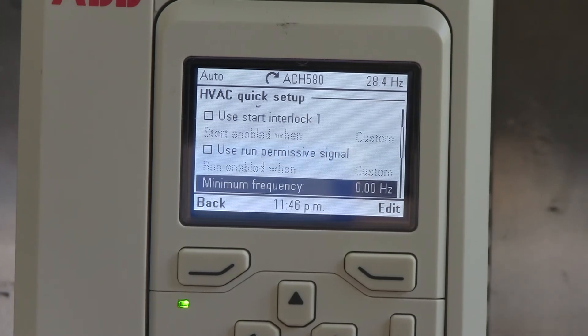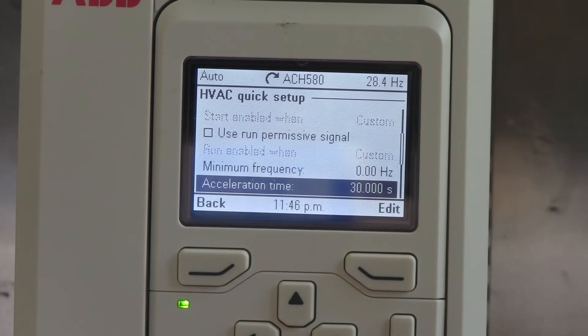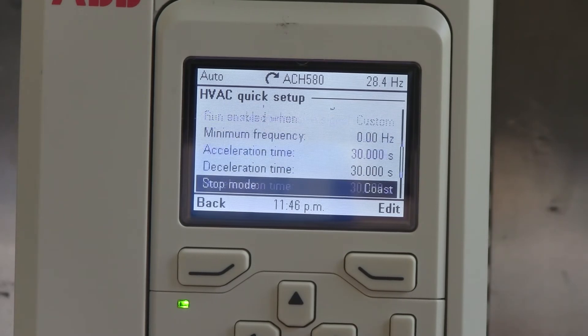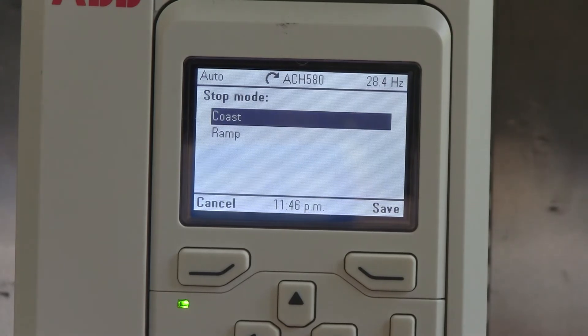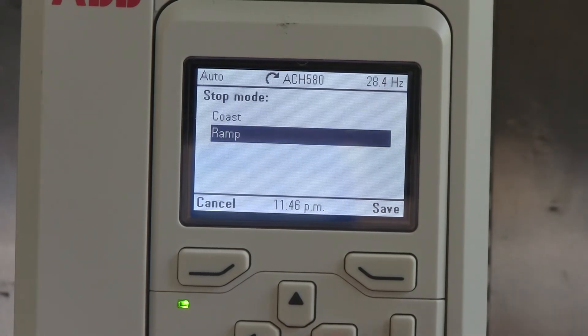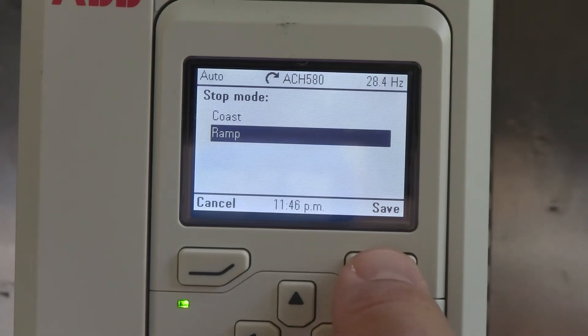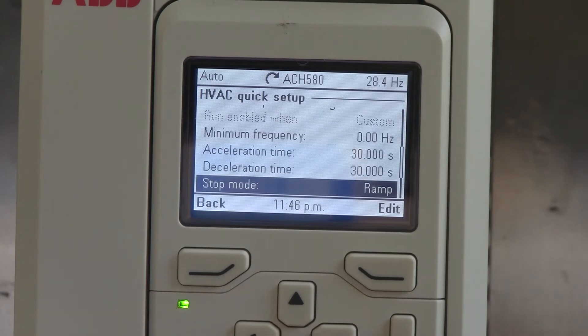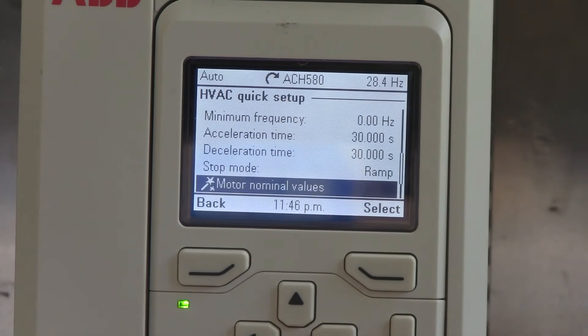You can adjust your minimum frequency, your acceleration time, deceleration time, your stop mode. If you wanted to run a ramp to stop for a pump or something like that, that's where you do this. Save that, and then hit the down arrow again, and then we can hit our motor data.